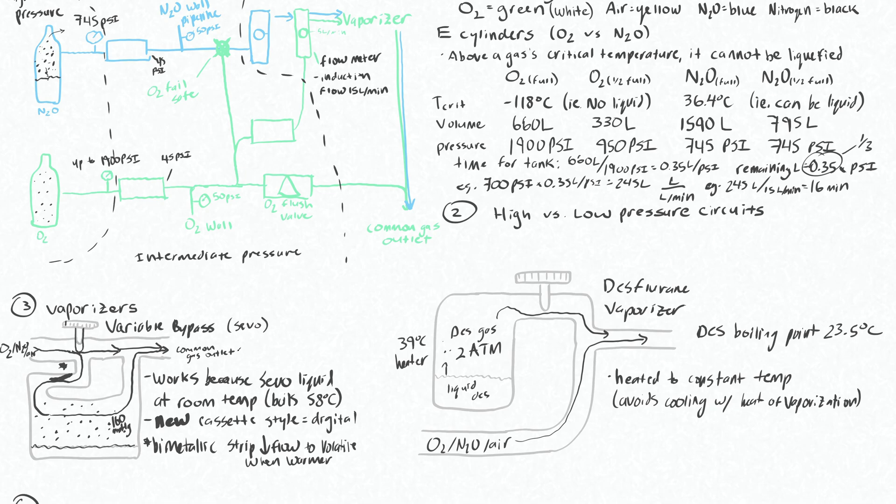This heat of vaporization that we talked about for des is of course also happening in the sevo vaporizer. When the sevo goes from the liquid to the gas phase, this temperature would drop a little bit, but then it is compensated by this bi-metallic strip.